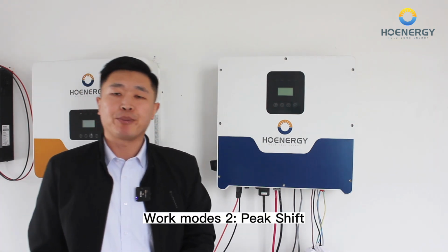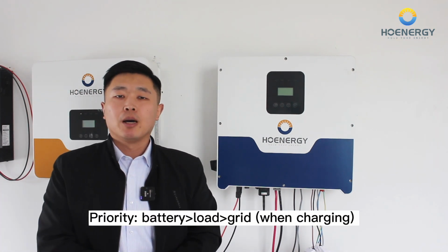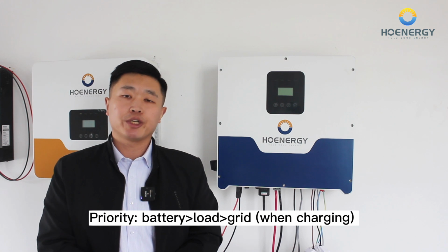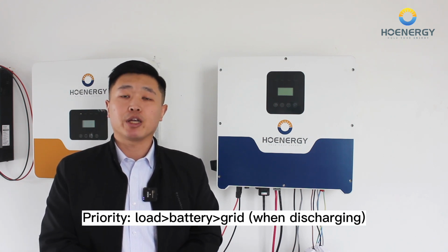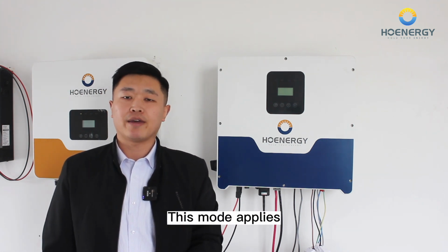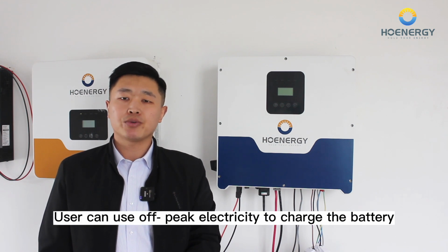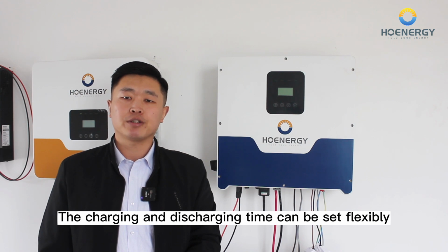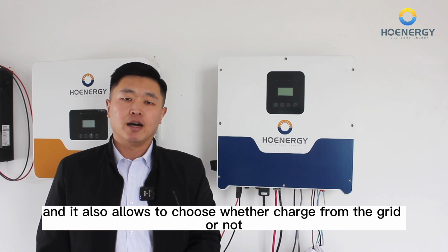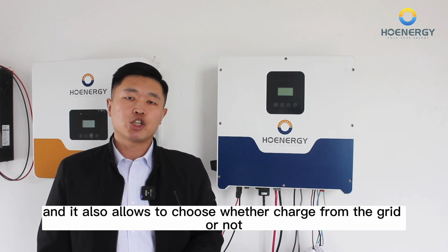Work mode 2, peak shift, priority: battery greater than load, load greater than grid. When charging, priority: load greater than battery, battery greater than grid when discharging. This mode applies the area that has electricity price between peak and valley. User can use off-peak electricity to charge the battery. The charging and discharging time can be set flexibly, and it also allows to choose whether charge from the grid or not.